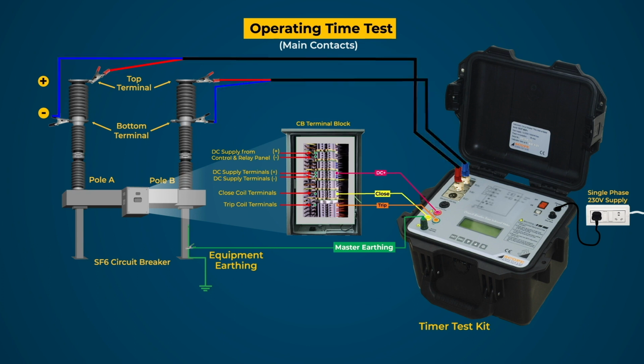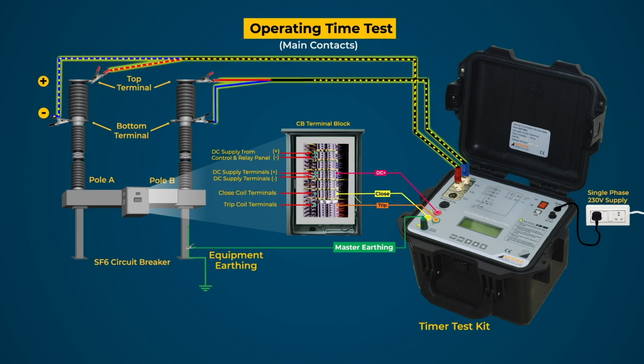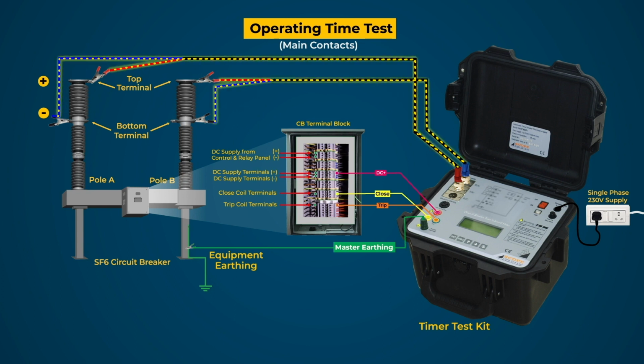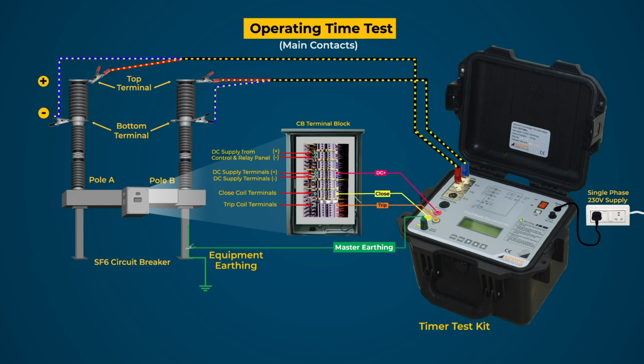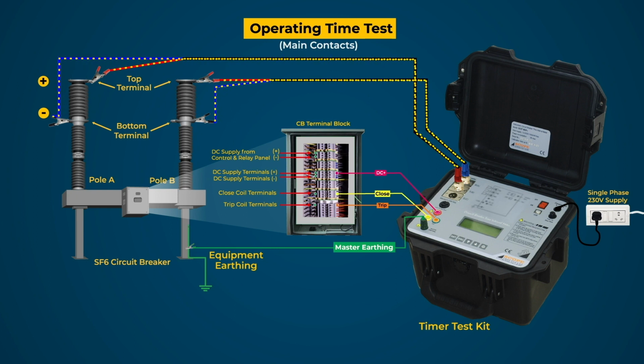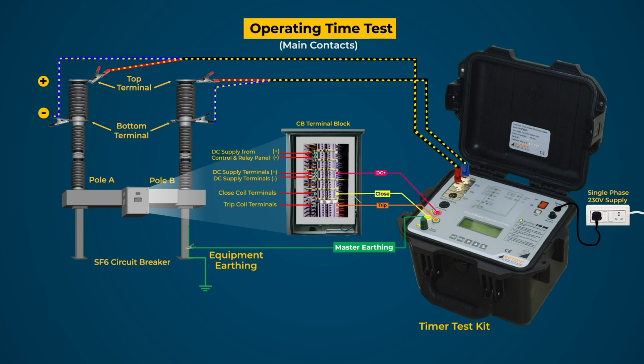The tester gives the trip or close open command to the breaker as selected, and low DC voltage is applied across the breaker contacts by the contact timing leads as an electrical signal to get the status of the main contacts. When the breaker changes its status, the tester senses the change in the electrical signal, and the timer measures the operating time of the breaker under test.